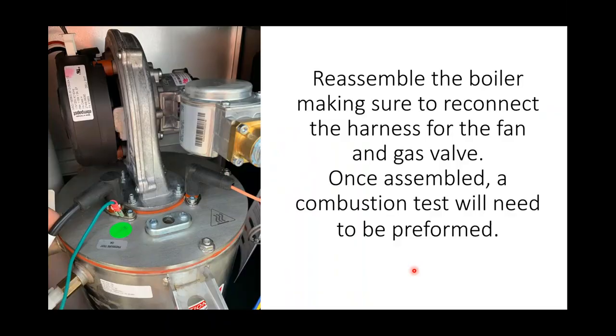So next, we want to reassemble the boiler. We basically want to take our process and do it in reverse. Put the harnesses back in the fan. Place the burner plate back on top of the heat exchanger. Put all of our bolts back in. Again, this back bolt is much easier to put on first, as we can still tilt and move the burner plate around, then do our other three.